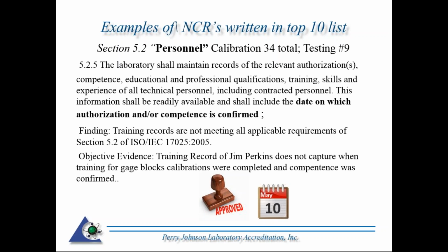So this particular nonconformance was written in regards to an employee, and actually it's for gauge blocks, that date was not captured. And you could capture that in many, many ways. For larger organizations, it could be captured in a matrix. Technicians down one side, disciplines on the other side with date competence captured. It'll be just a paper and a sign off. Employee signs off that they understand it, and the laboratory supervisor, technical quality manager, somebody else signs off and gives that date competence that they determine that employee is competent to perform calibrations independently on behalf of their company.